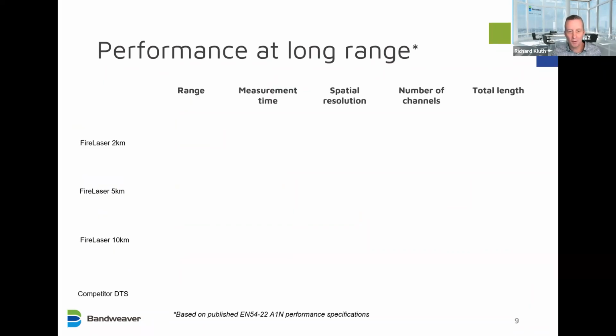That leads to the next question: what kind of performance can you get at the longer ranges? We'll look at a number of the fire laser systems up to 10 kilometers, and then compare with other fiber optic competing DTS systems. If we look at the 2 kilometer fire laser, as the name suggests, you measure 2 kilometers per optical channel. You get a measurement every 5 seconds and a measurement point every 1 meter. You can have up to 4 channels per unit, which means a total coverage of 8 kilometers per unit, or 8,000 sensing points.